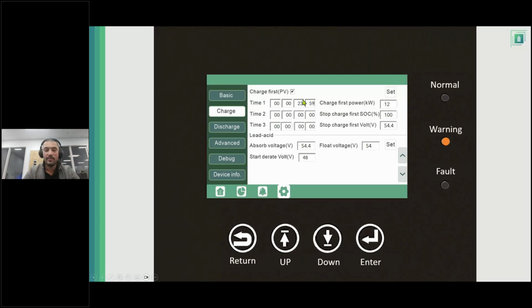So basically, I have the system that is not going to use the battery at all, 24/7, until there is an outage. I do recommend, however, that the battery cycles 10% every day. It's not mandatory, but it's better for the SOC calibration. If you have a battery, use a battery. Not using the battery doesn't necessarily guarantee more life, because with their chemistry, you need to use batteries in some way, form, or another. So I recommend using 10%. Again, not mandatory, but it's how I personally have used the system.